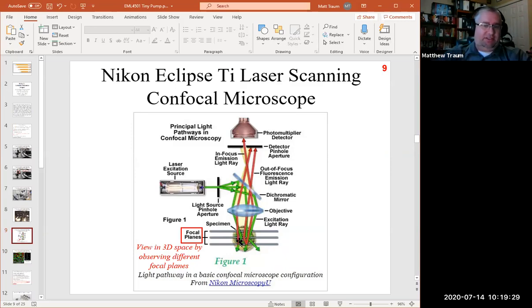That light that comes off of the cells then goes through the optics again, gets refocused, and at this point goes through this mirror because it's at the correct angle and the correct wavelength to pass through the mirror. And then here's the really cool confocal part: the optics are set up in such a way that most of those light beams don't actually reach the detector, the photomultiplier detector. A lot of them are just stopped by a pinhole aperture. But one point of light, one ray of light, actually does go through the aperture, and that ray of light is the one that's collected by the photomultiplier detector, which is a computer system basically that takes those individual photons that are collected and reconstructs the image.